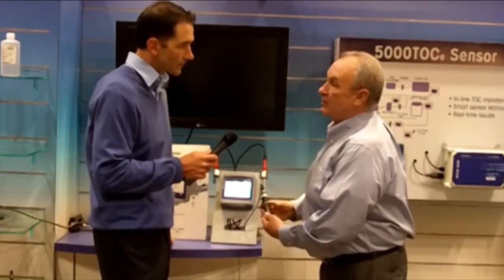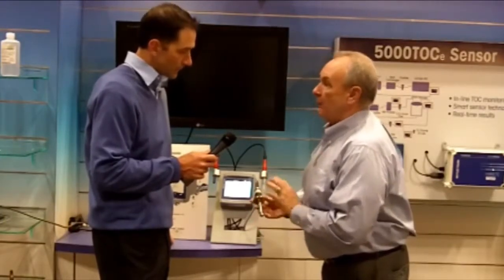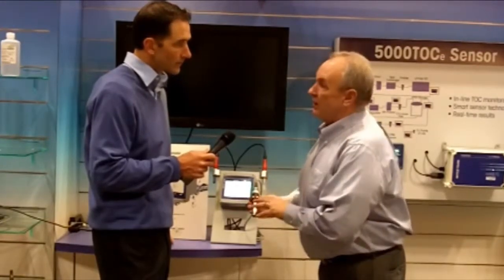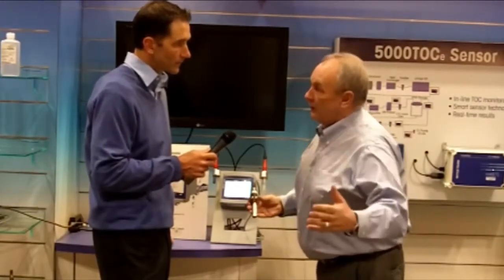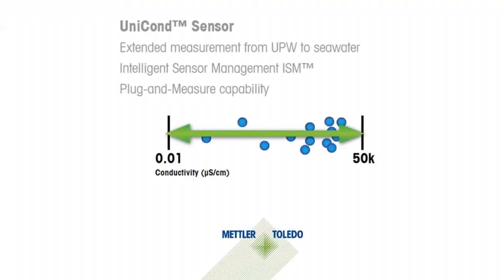You also eliminate what's called polarization error. Polarization error previously limited a sensor to only be measured in the ultra-pure water range. Now, with UniCond, we can measure from ultra-pure water to sea water with a 33% increase in accuracy.